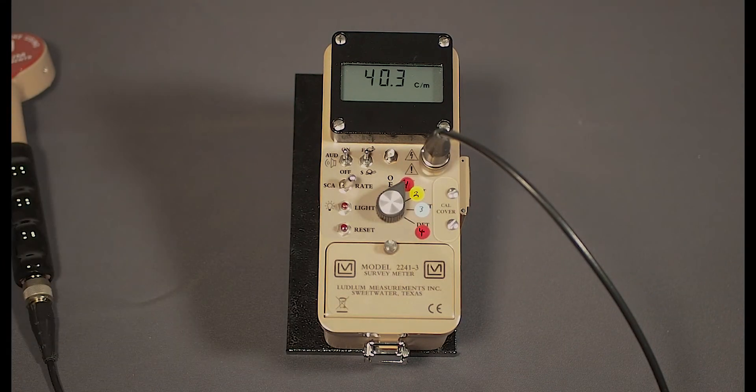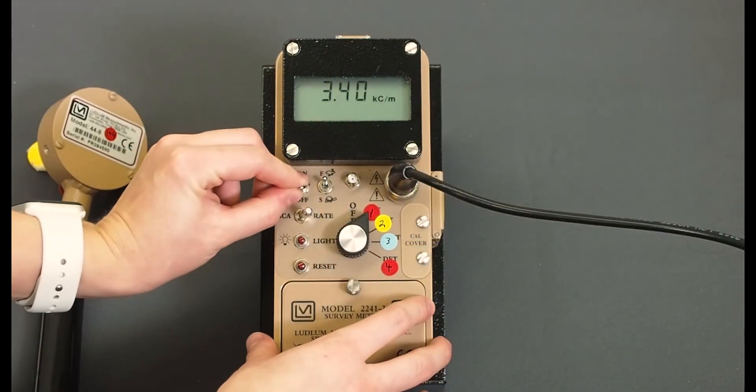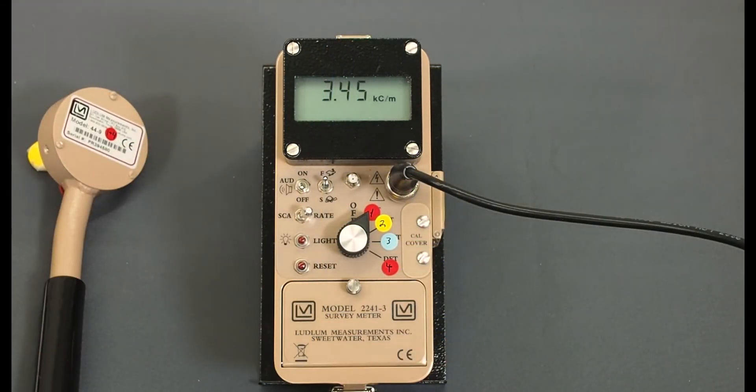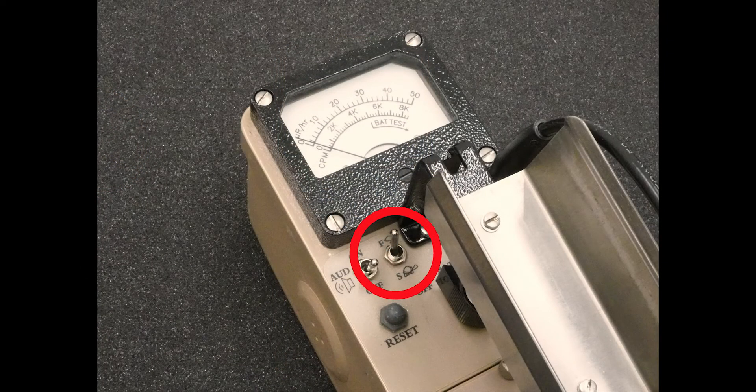The 2241-3 has a rotary switch for turning the meter on and selecting the detector setting. There is an audio switch to turn the audible clicks on and off. A switch labeled FS controls the response time of the instrument.